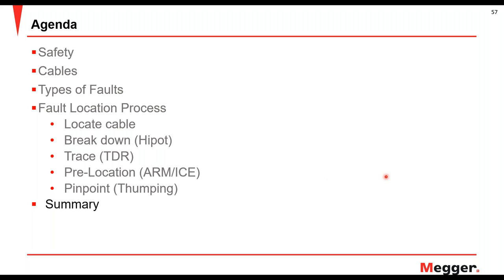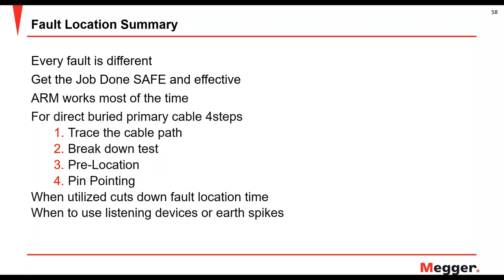Finally, the summary: every fault is different. You need to know that the whole reason for cable fault location is to get the job done safely first and effectively. Arc reflection works most of the time — if you can't arc reflect, try ICE. This is for direct burial cable. There's a four-step process: I recommend tracing the actual cable path itself, then at minimum do the high pot to see where it flashes over.